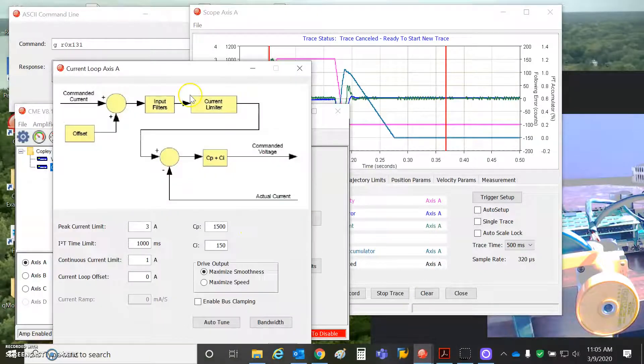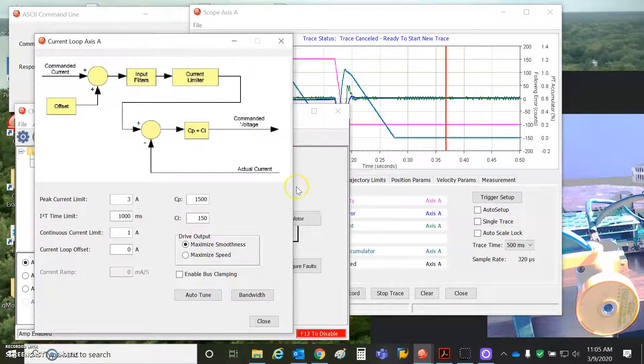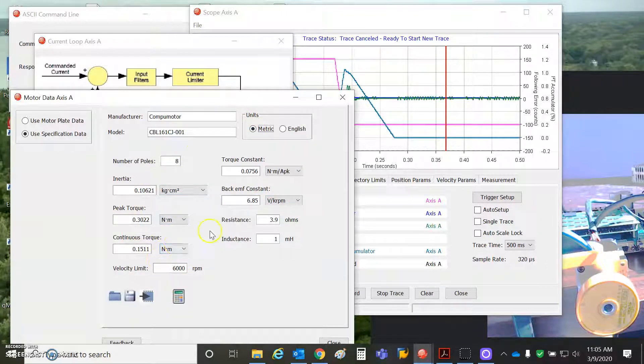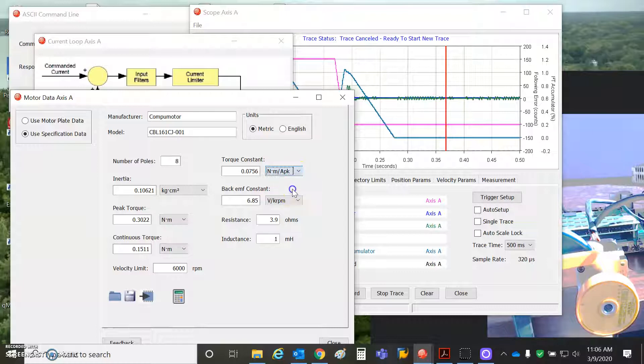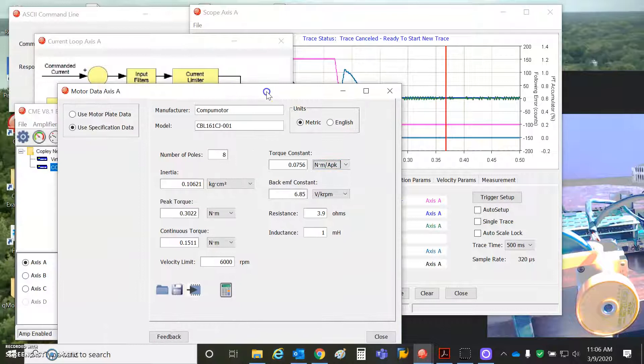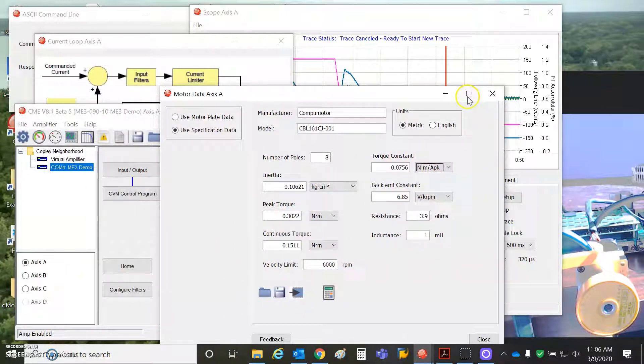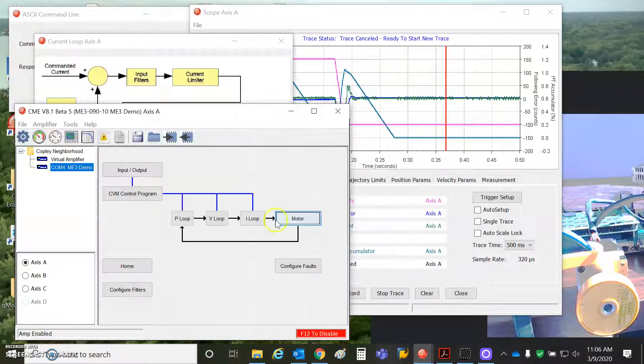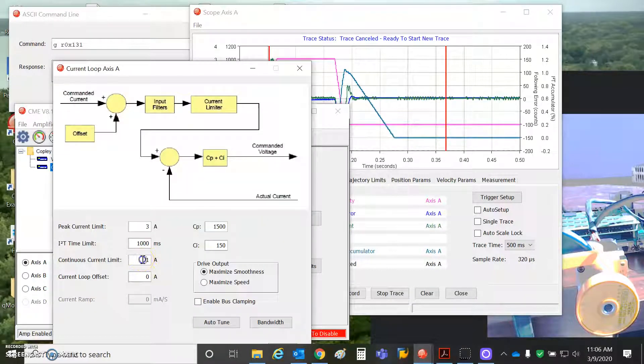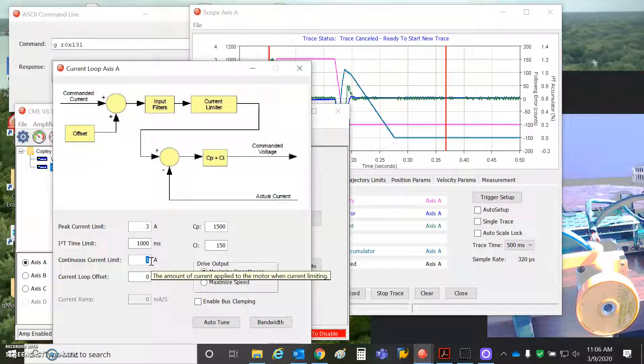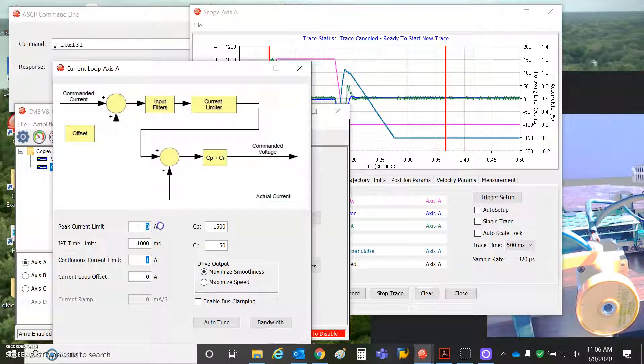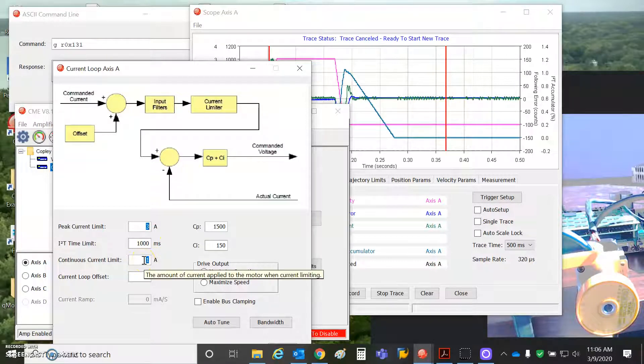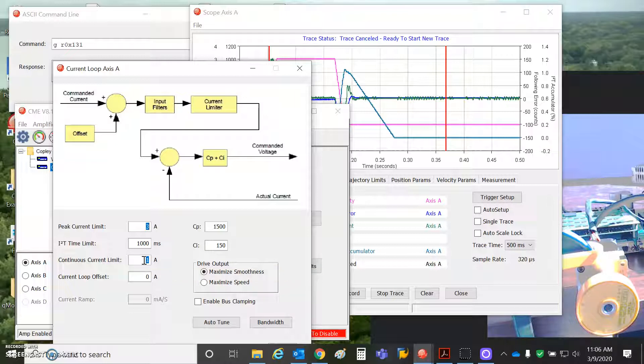And so I'll show you where we do that here. Normally, we put in the motor data of the Newton meters and Newton meters per amp peak or RMS, depending on how they specify it. But a lot of times people don't bother to put the units in there, so we don't always know. Now, just for testing purposes, I've set the continuous current to 1 amp peak and 3 amps peak. And by that, I mean peak of the sine, not RMS. If I put 0.707 in here, that would be amps RMS. If I put in 1 amp, that's the magnitude of the vector that we're rotating to the brushless motor.